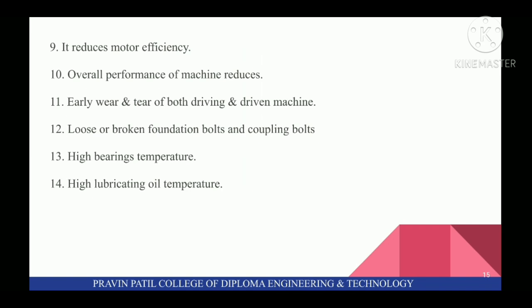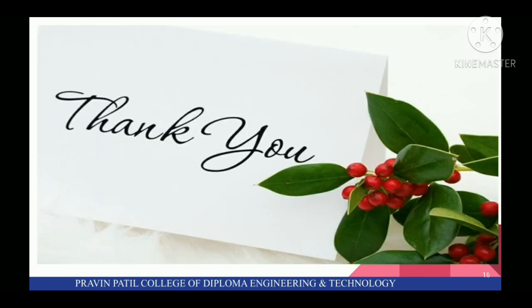Eleventh is early wear and tear of both driving and driver machine. Twelfth is loose or broken foundation bolts and coupling bolts. Thirteenth effect is high bearing temperature. Fourteenth is high lubricating oil temperature. So these are the effects of misalignment. Thank you.